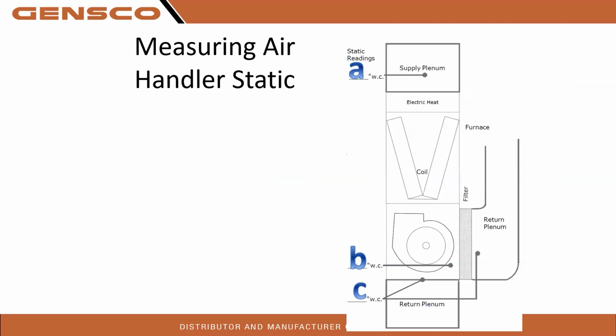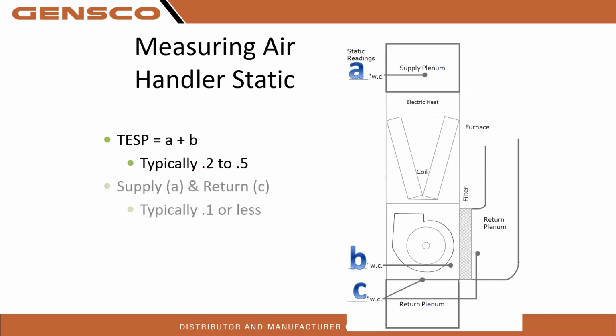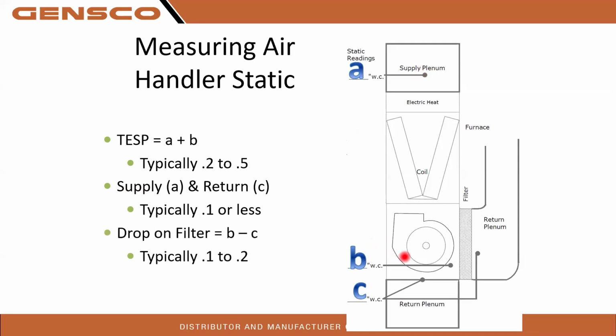Measuring air handler static. Again, the coil is built into this, so it is tested with the coil. So A to B across the coil, there is some drop for the electric heat too. So we're going to be 0.2 to 0.5. Supply and return is typically 0.1 or less. Drop on the filter, typically 0.1 to 0.2. That could change on the different filters.